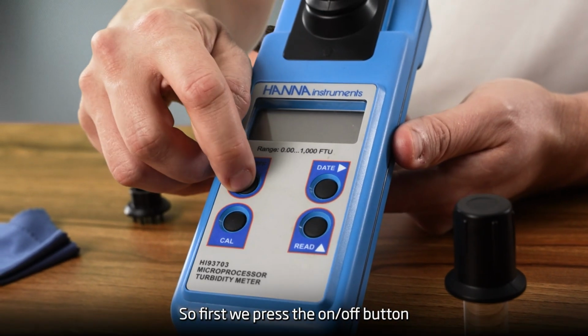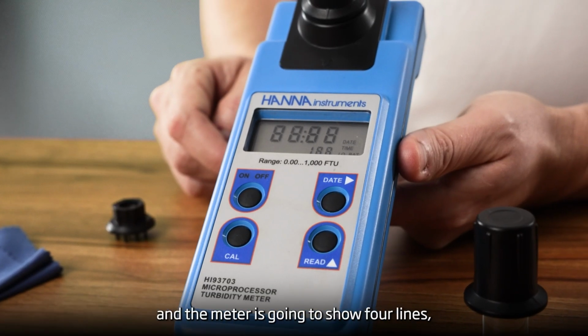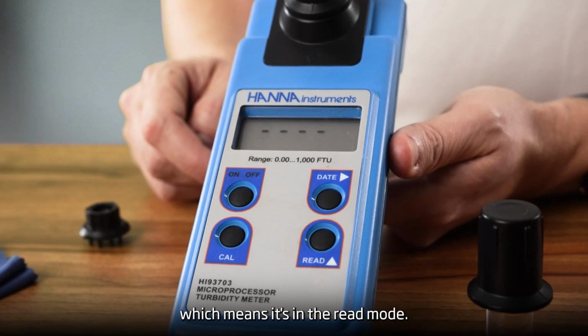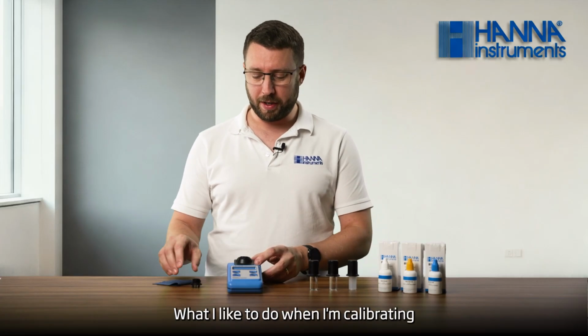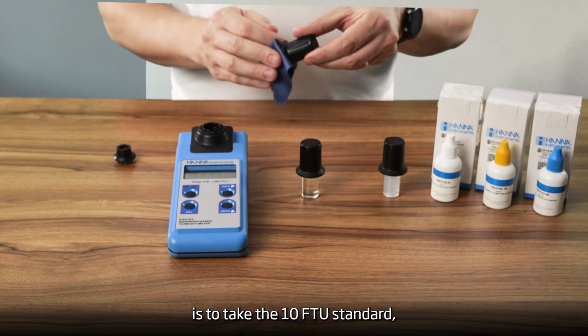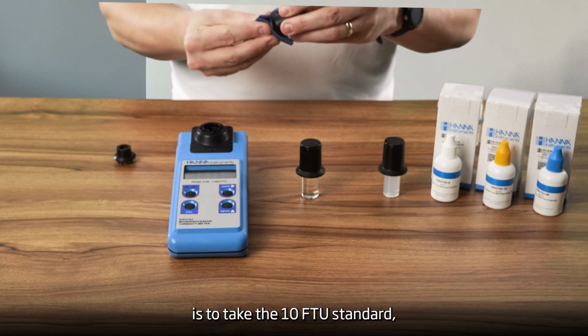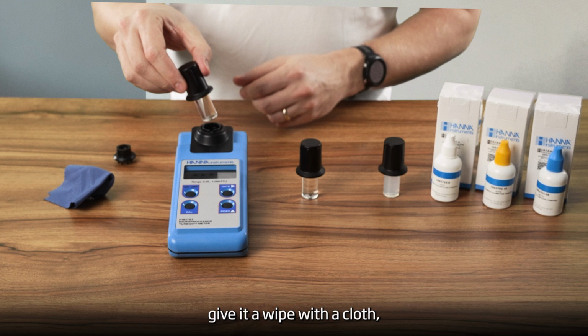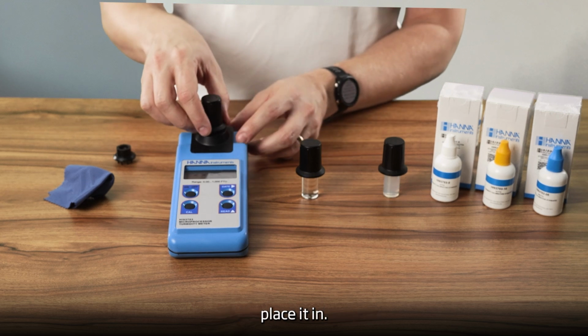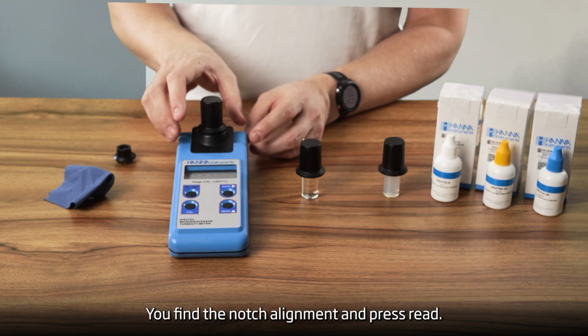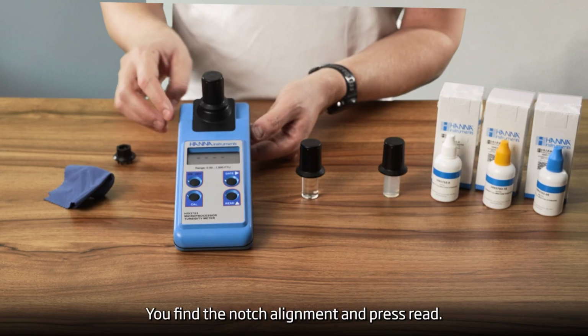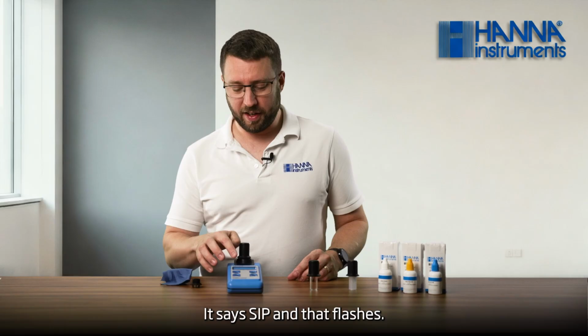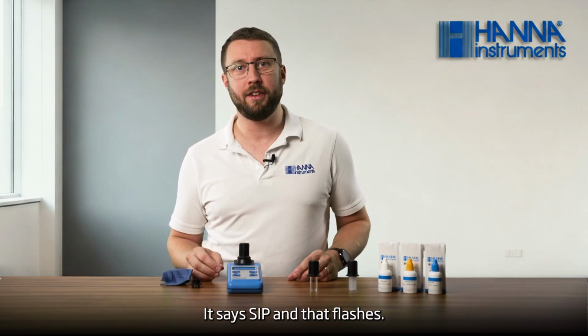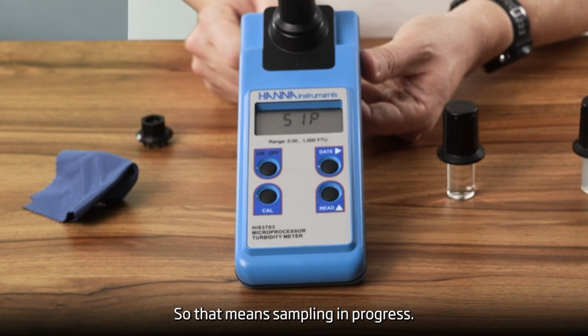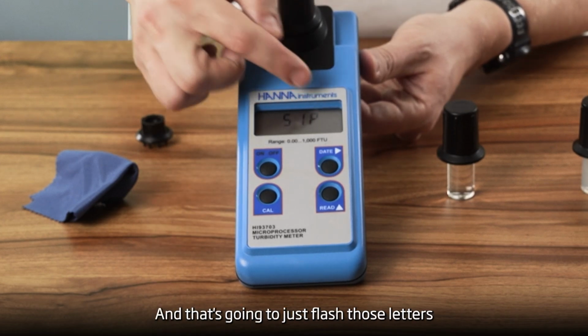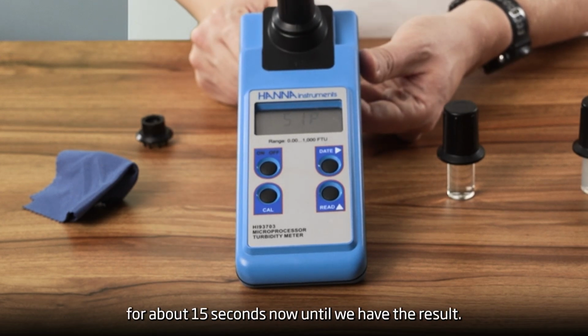So first we press the on-off button and the meter is going to show 4 lines, which means it's in the read mode. What I like to do when I'm calibrating is to take the 10 FTU standard, give it a wipe with a cloth, place it in, you find the notch alignment and press read. It takes about 15 seconds. It says SIP and that flashes, so that means sampling in progress, and that's going to just flash those letters for about 15 seconds now until we have the result.